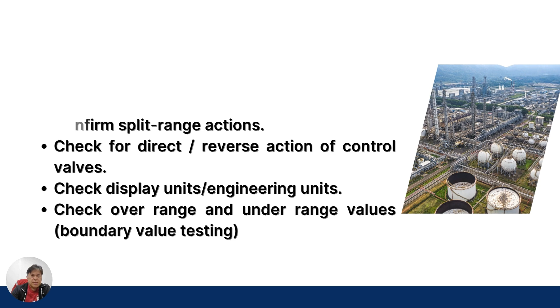Check the PST, meaning if you are in commissioning and the engineer tells you, so how about our PST? It's completed, testing is done. So that is the partial stroke test. Okay. Function for emergency shutdown valve and blowdown valve. This is very important, why we do the testing in this partial stroke test. Don't ask me how to do the partial stroke test. Okay? So search and check all of my videos, and then you will know everything. So the process of learning, guys, is step by step. Okay? So from the engineering, construction, implementation, pre-commissioning stage, commissioning stage, handover. All right. So closing timing of emergency shutdown valves and opening timing of blowdown valve.